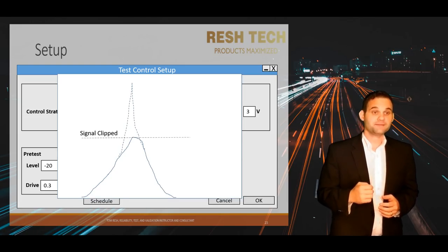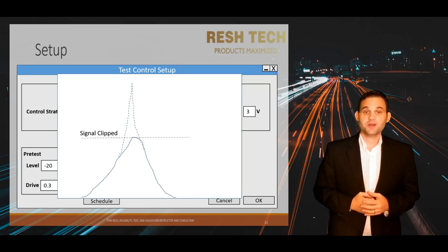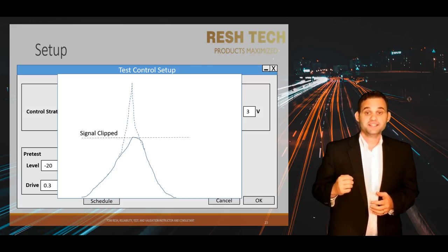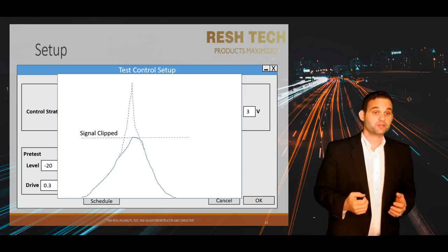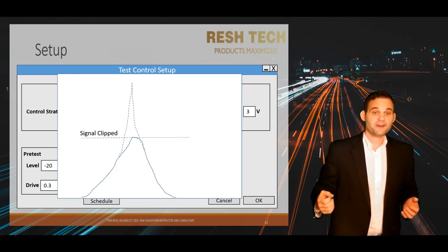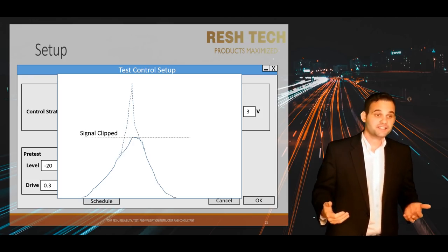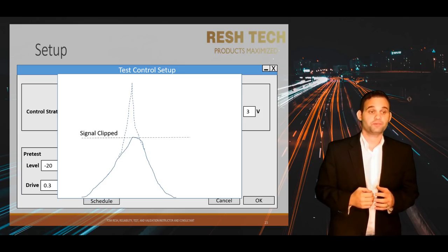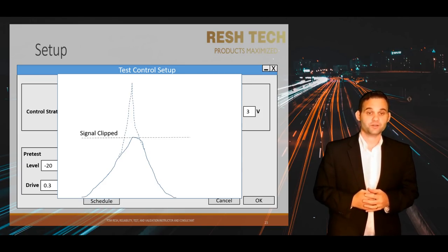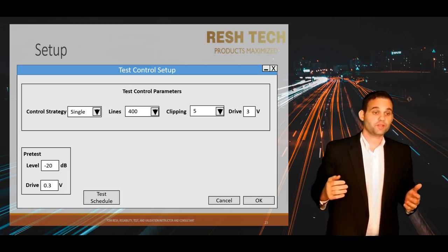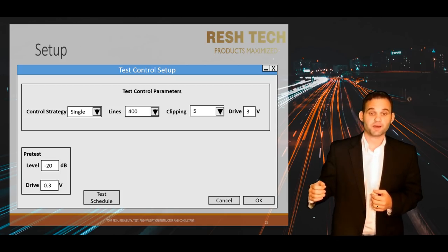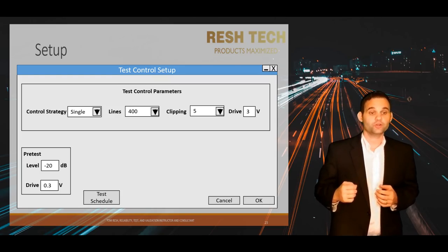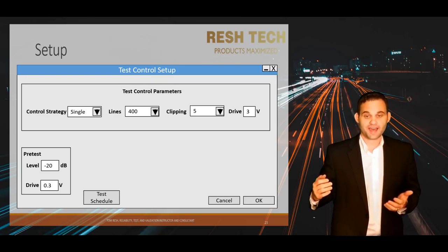Next up is sigma clipping. Sigma clipping prevents large acceleration spikes during a random vibration test. Setting this value too high can damage your system or product if a large spike occurs, and setting it too low will cause the drive signal to no longer be a close approximation of a random signal. So you need to balance between removing dangerous random spikes and not over-clipping your signal to the point it loses its randomness.